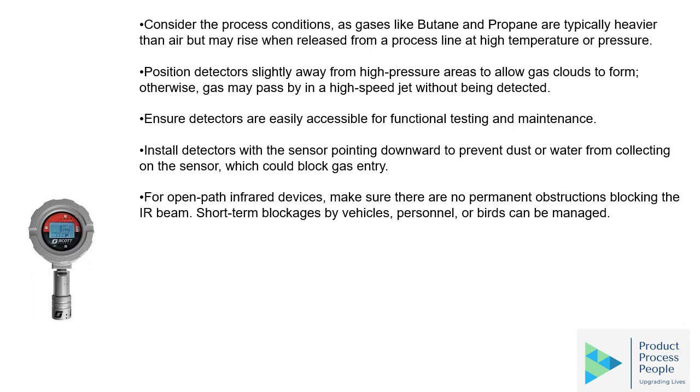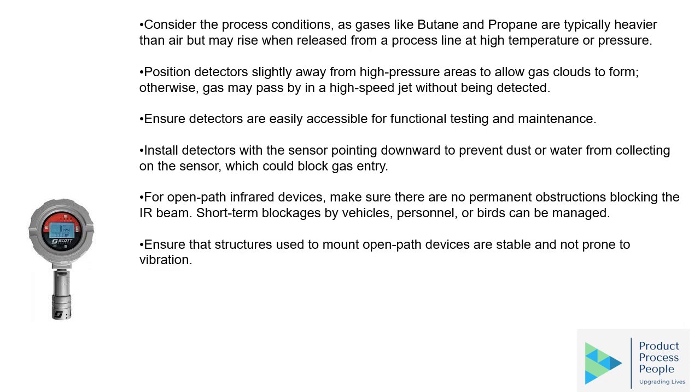For open path infrared devices, make sure there are no permanent obstructions blocking the IR beam. Short-term blockages by vehicles, personnel, or birds can be managed. Ensure the structure used to mount open path devices is stable and not prone to vibration.